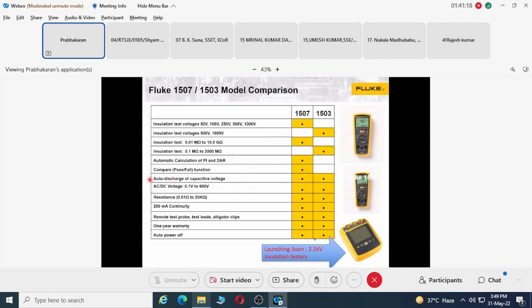Both these models come with auto discharge, so they will not hold any current when you are doing high voltage testing. The DUT may absorb some current, and it may give a shock if the tester doesn't have auto discharge. That's why you need to be very careful when choosing high voltage testers or insulation testers, otherwise you may end up getting shocks.